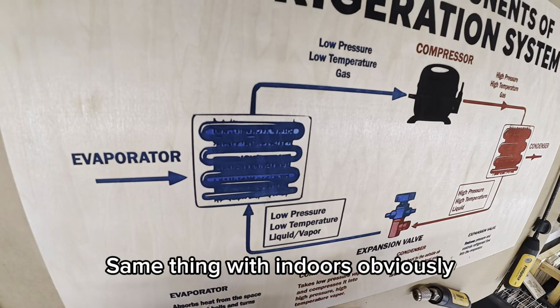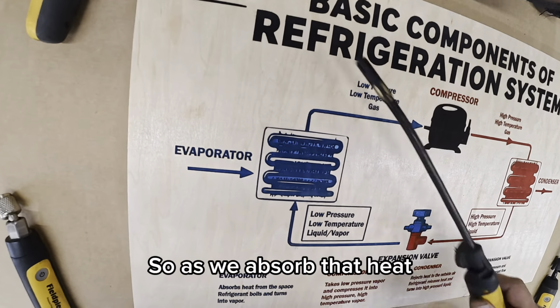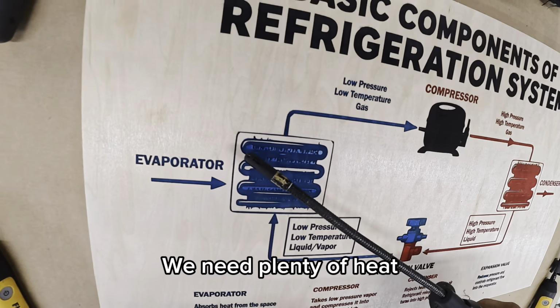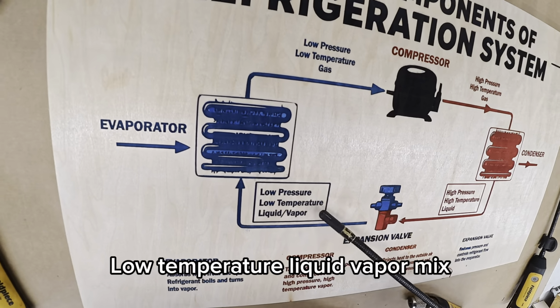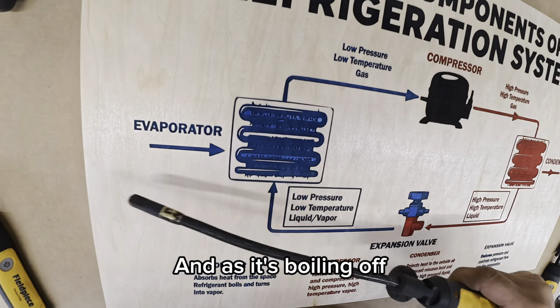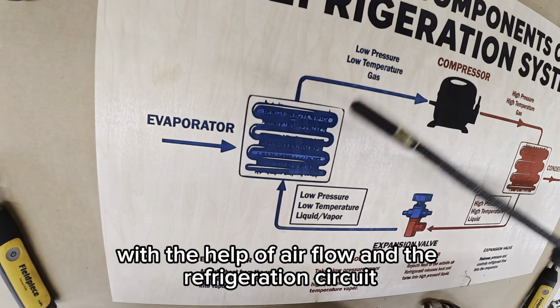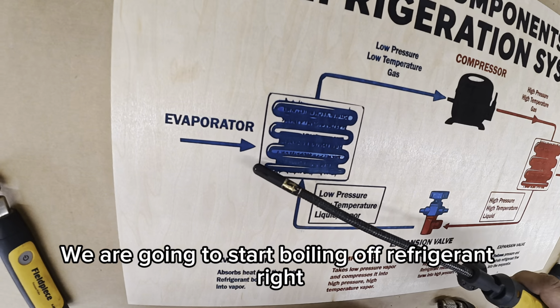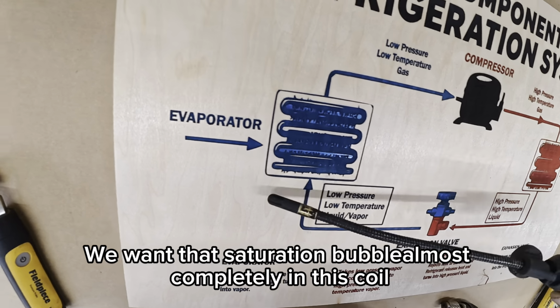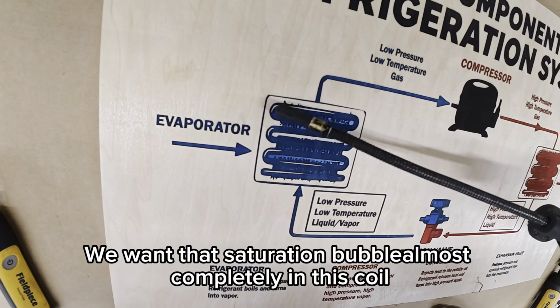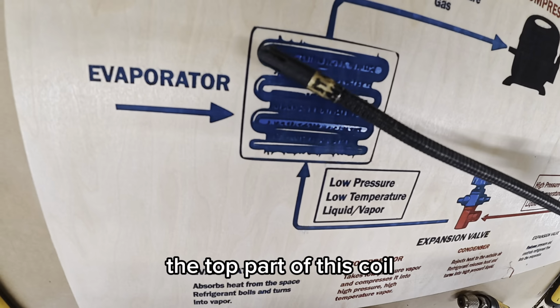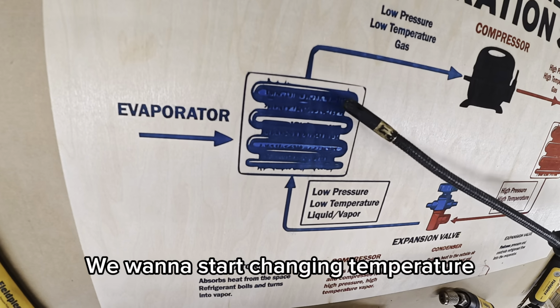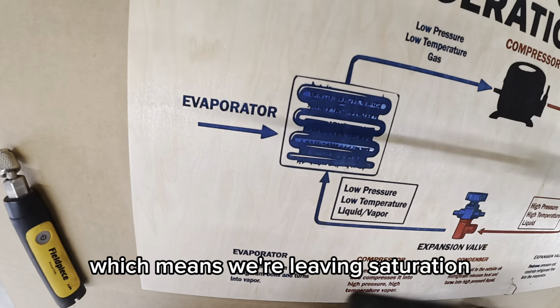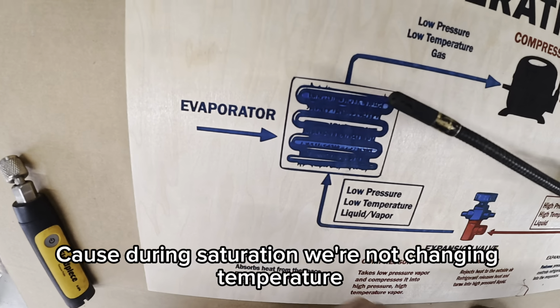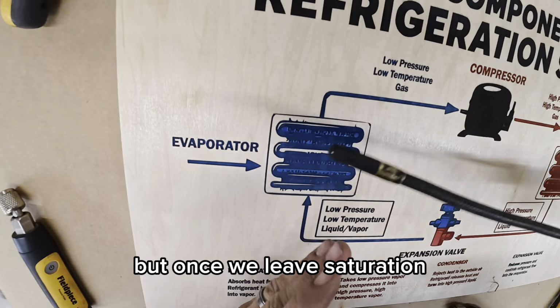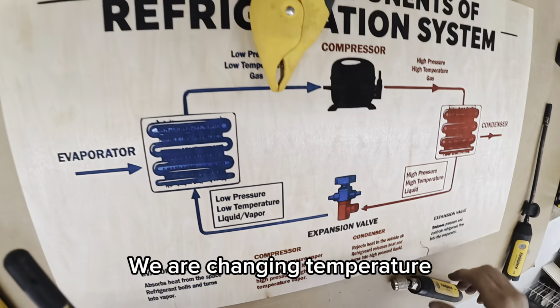Same thing with indoor, obviously very important. So as we absorb that heat, we need plenty of heat so that when we fill this coil with low temperature liquid vapor mix, and as it's boiling off with the help of airflow and the refrigeration circuit, we are going to start boiling off refrigerant, right? We want that saturation bubble almost completely in this coil, except for the top part of this coil. We want to start changing temperature, which means we're leaving saturation, right, guys? Because during saturation, we're not changing temperature. But once we leave saturation, we are changing temperature.